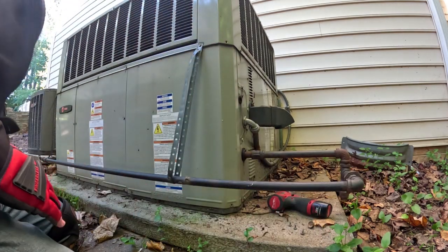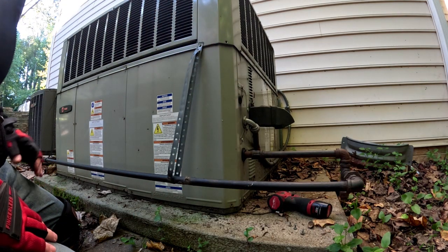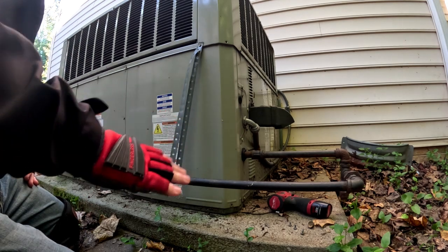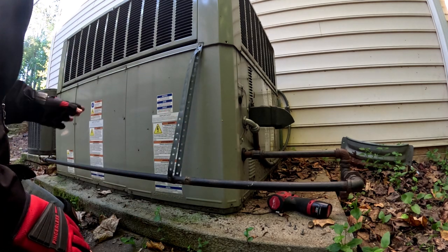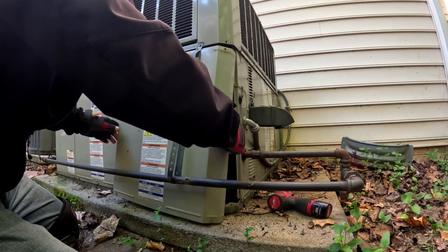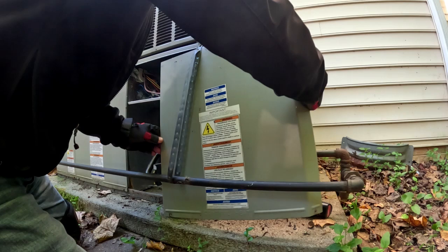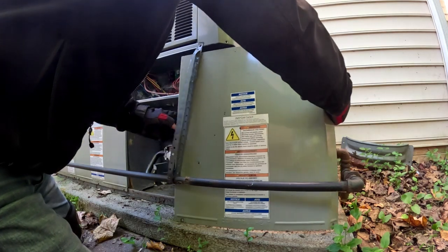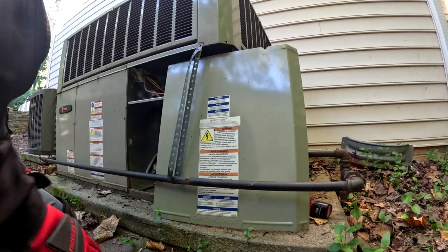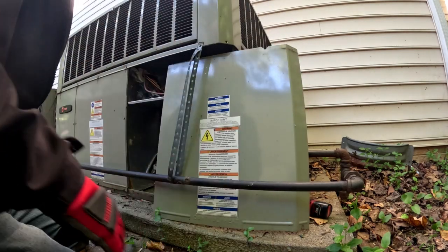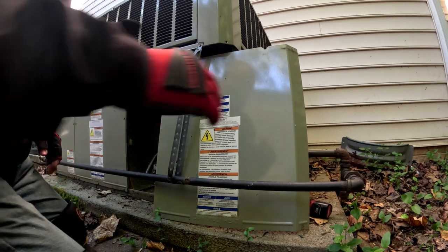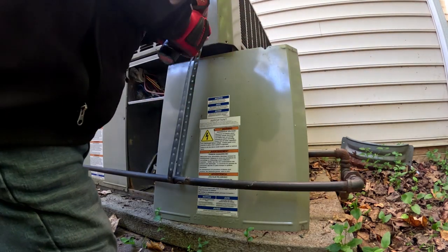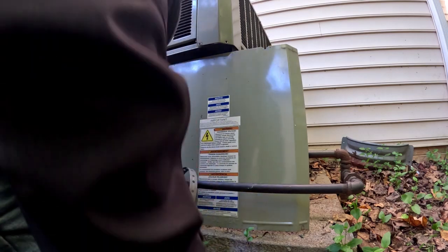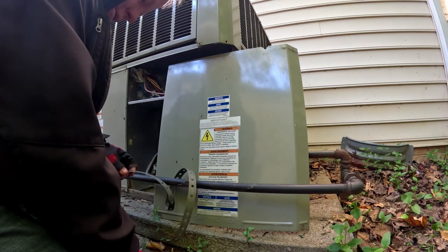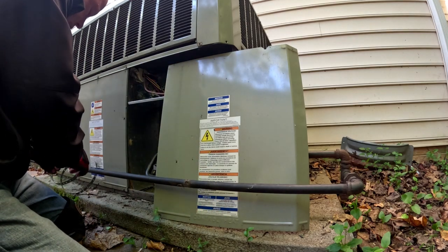They said the blower wouldn't run, or they tried turning the fan on and didn't hear anything happening out here, no air blowing. So, this gas line is running right in the front of the unit, so I'm going to take this off temporarily to get this door out of the way. Just a little strap. There we go.